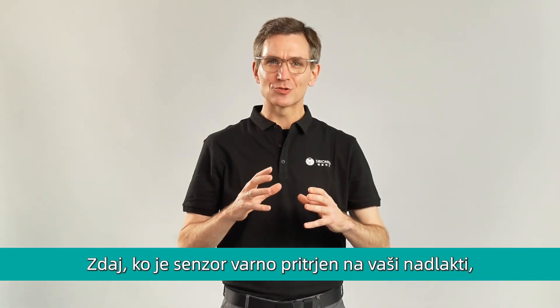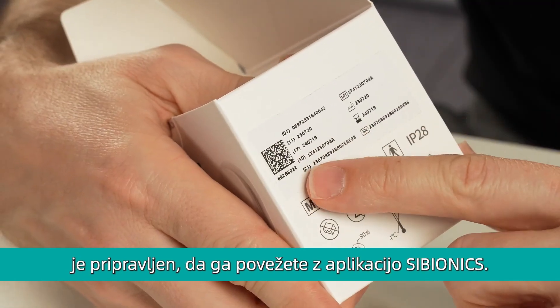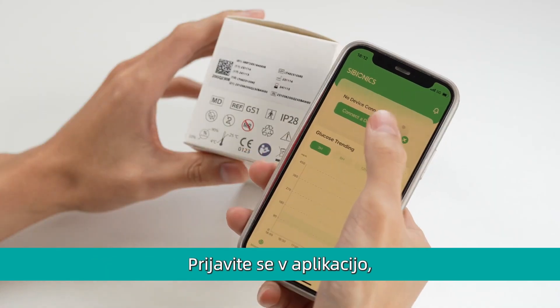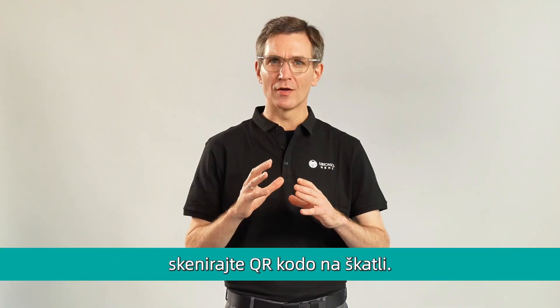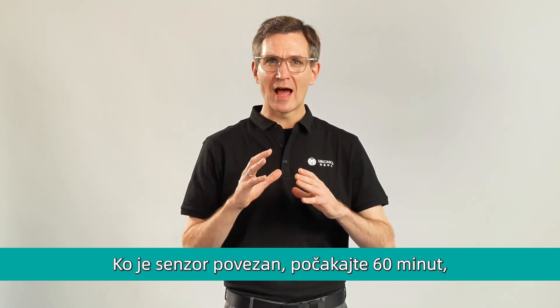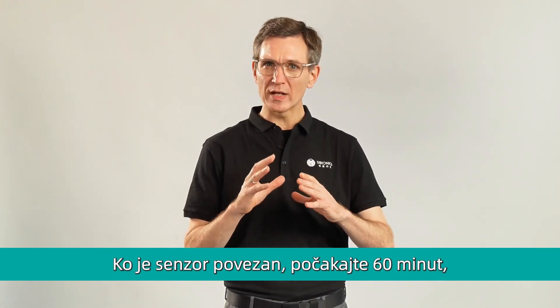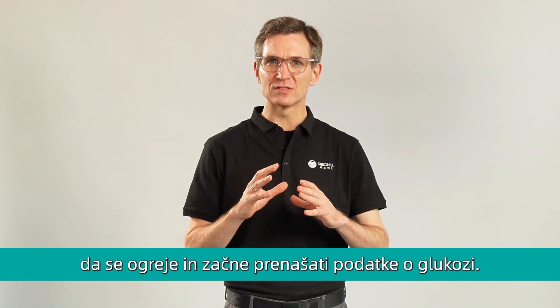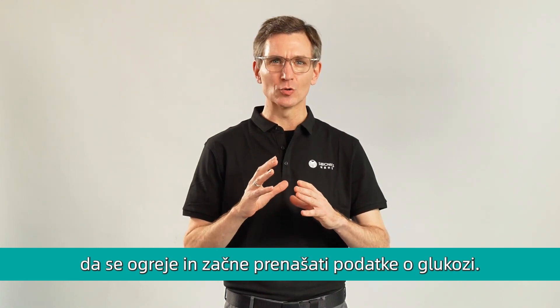Now that the sensor is securely applied to your arm, it's ready to pair to the SIBIONICS app. Log in to your SIBIONICS app and scan the link code on the CGM package. After connecting the sensor to the SIBIONICS app, wait about 60 minutes for the sensor to warm up and start transmitting your glucose data.